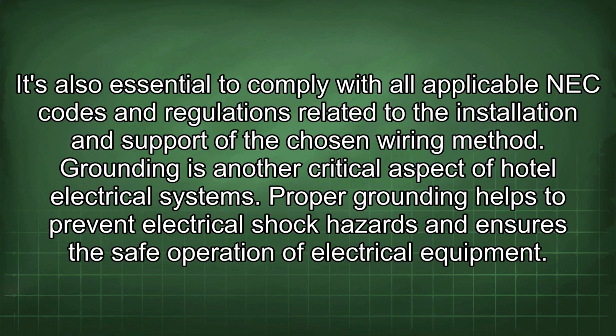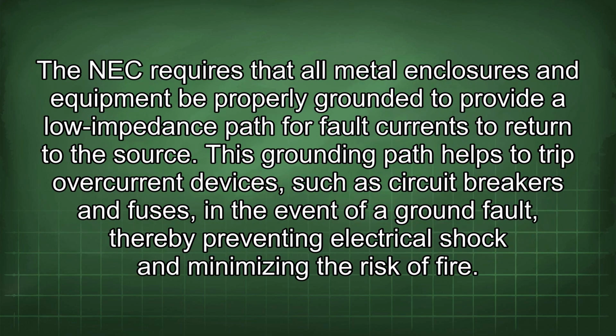It's also essential to comply with all applicable NEC codes and regulations related to the installation and support of the chosen wiring method. Grounding is another critical aspect of hotel electrical systems. Proper grounding helps to prevent electrical shock hazards and ensures the safe operation of electrical equipment. The NEC requires that all metal enclosures and equipment be properly grounded to provide a low impedance path for fault currents to return to the source. This grounding path helps to trip overcurrent devices, such as circuit breakers and fuses, in the event of a ground fault, thereby preventing electrical shock and minimizing the risk of fire.